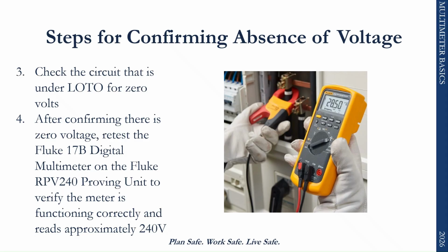Once the meter has been verified, you can move to the equipment that has been placed under lockout/tagout. Use the meter to test the circuit and confirm that the reading shows 0 volts. After confirming that the circuit is de-energized, the final step is to return to the proving unit and test the meter again. The meter should once again read approximately 240 volts. This final check confirms that the meter remained operational during the testing process and that the absence of voltage reading was accurate.